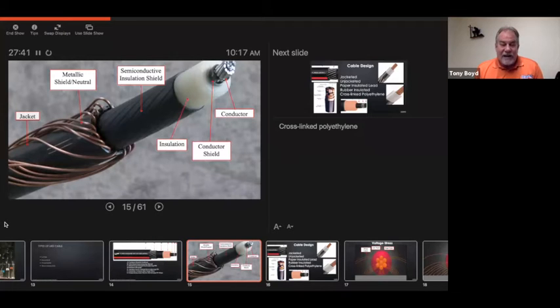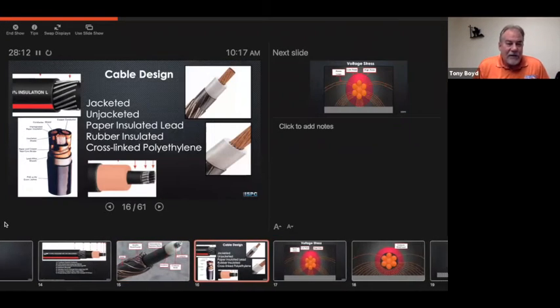Talk a little bit more about that when we get into the stresses, but you see on this one, just like the last cable, the conductor, and then the conductor shield, and then the insulation, the semiconductor insulated shield, and it is a semiconductor, even though it's made of a rubber compound. It will still conduct, and we'll talk about the purposes of that in just a little bit. We have the metallic shield, neutral conductor, and then the jacket, just like the other cable on here.